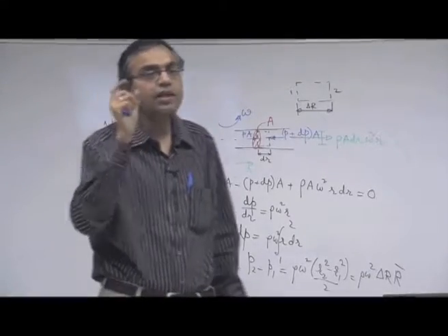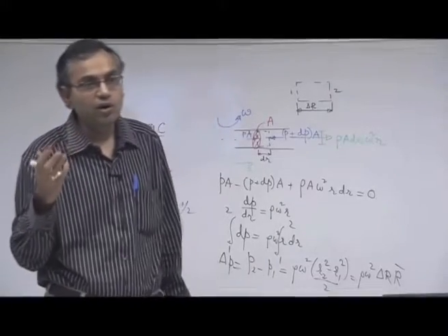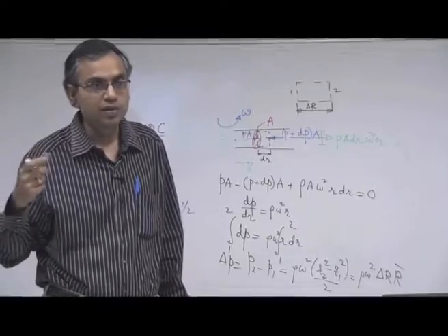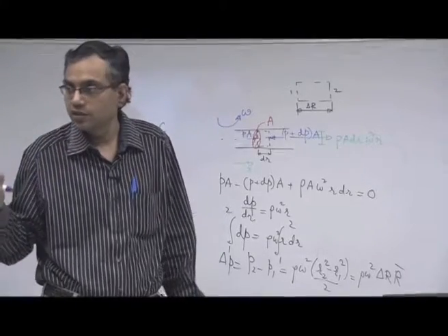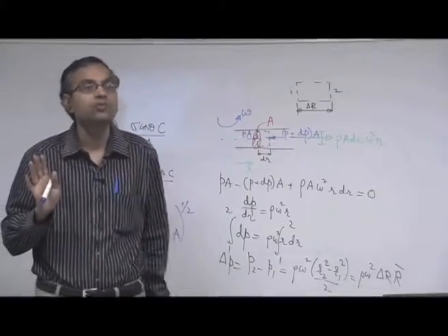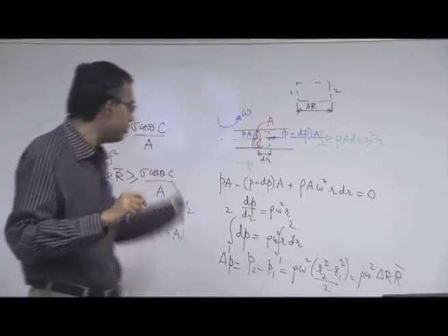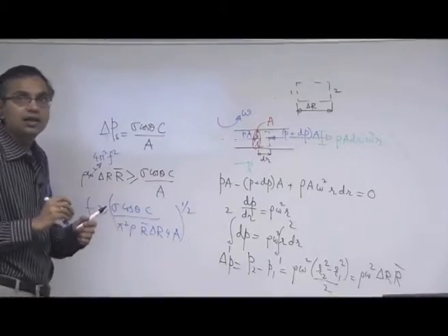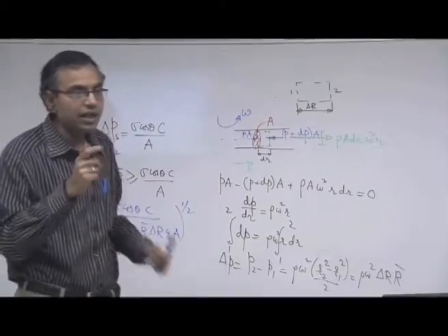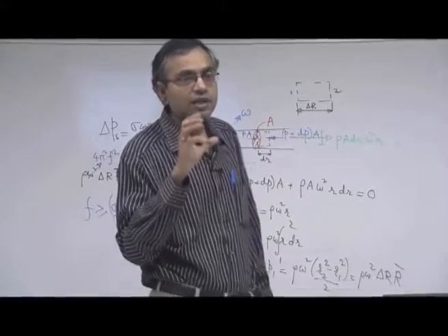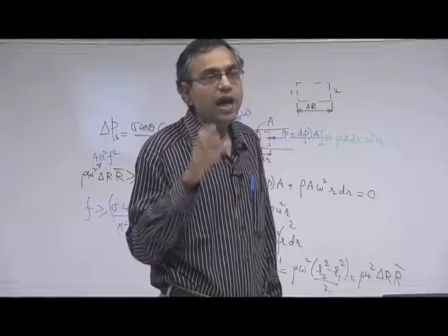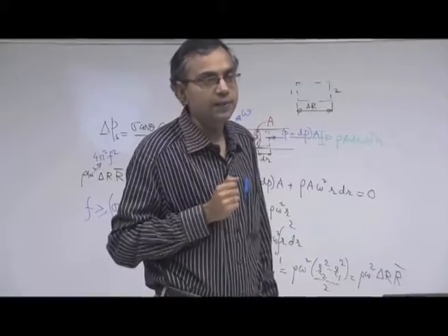This is a very basic design parameter, right. You must know the speed at which you should rotate the disc so that the fluid will start moving, otherwise you cannot do any fluidics with it. If you want to do fluidics with it, you must first make sure that the fluid moves, and this is a very simple design consideration. The fluid is designed to move radially outwards depending on at what speed you start moving it.